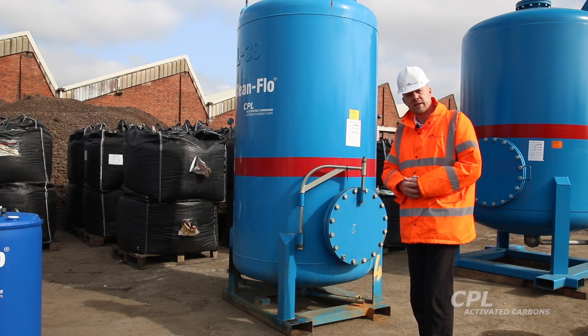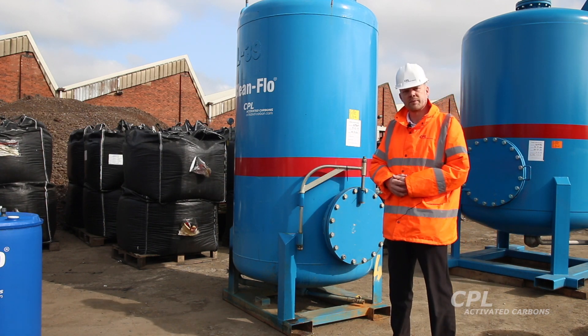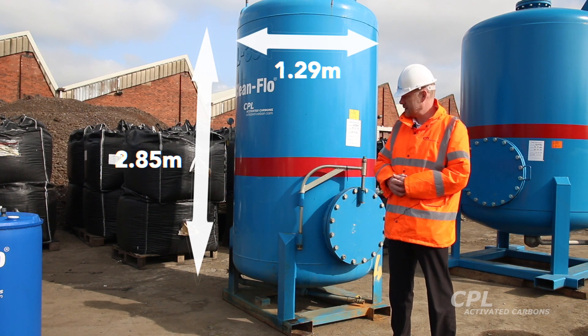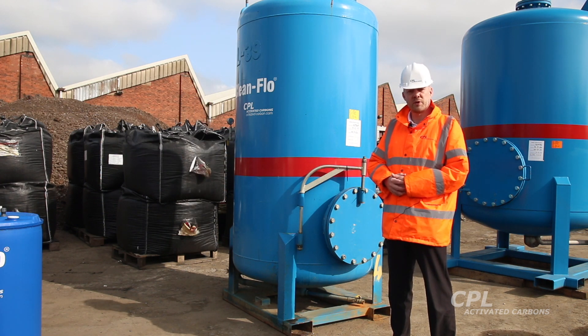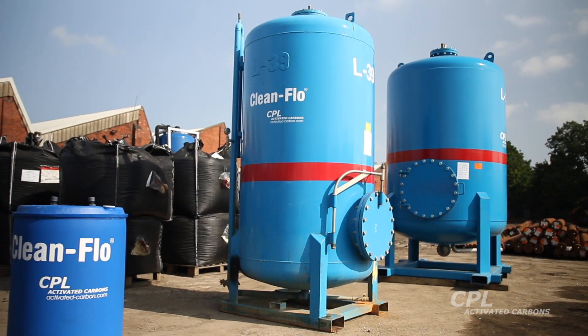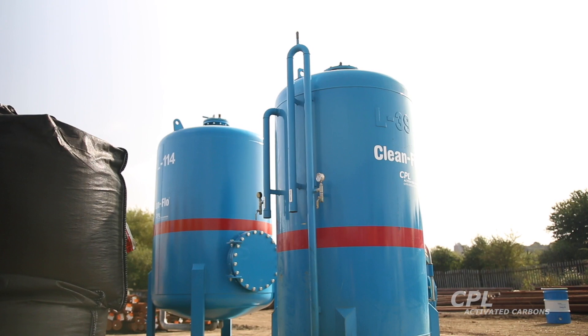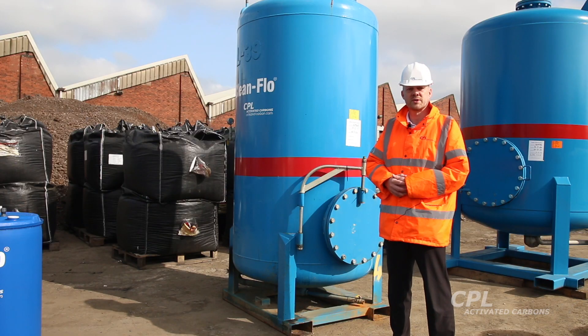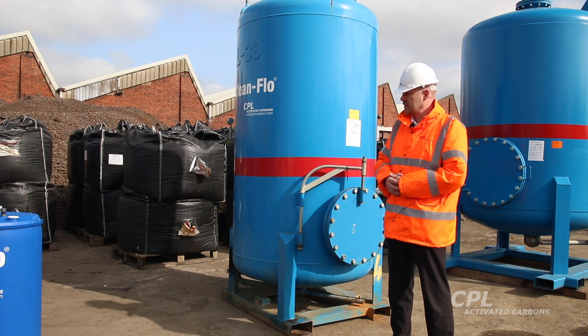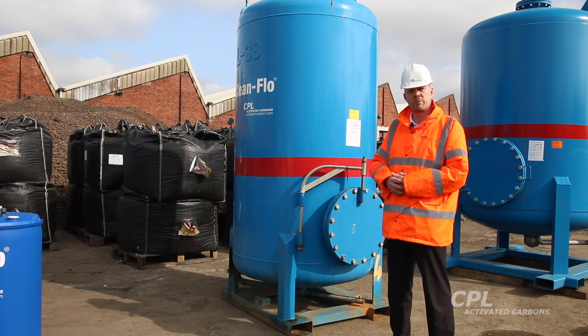This Clean-Flo unit here is a two-cube Aquasorba unit. It stands 2.85 metres high and 1.29 metres wide, contains two cubic metres of our Filter Carb activated carbon, and is delivered to site filled ready for use and connection to your existing pipework via two-inch BSP female adapters. It operates in a downflow direction and has an anti-siphon loop to prevent the carbon bed getting dry during periods of inactivity.